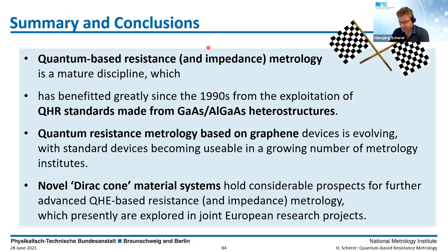Okay, we have to compare this quantum system to conventional, non-quantum systems. If you speak about a precision of 10 to the minus 6, or 1 ppm, you will find that conventional resistors, let's say secondary resistor standards, have sufficient stability to compete with these quantum systems. Or in other words, you can use a very simple and small box, like 10 times 10 times 10 centimeters, a standard resistor which you can buy, that you calibrate once, which has a good stability once thermalized or thermostated.